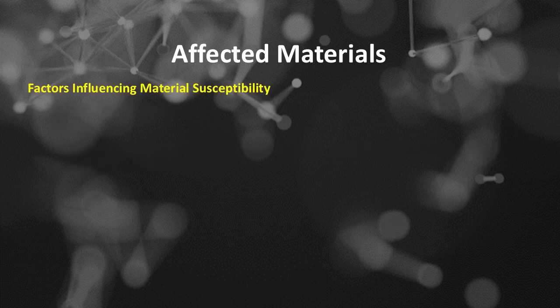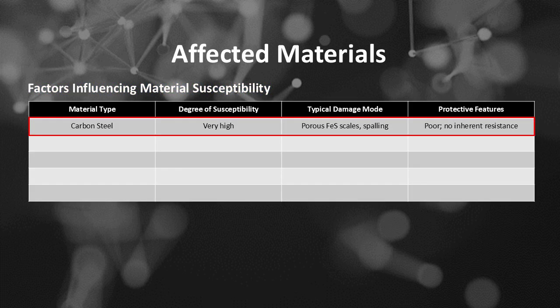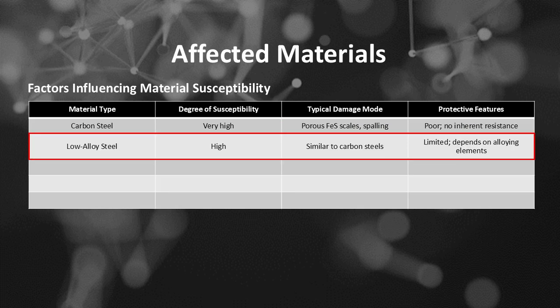Factors influencing material susceptibility. If material type is carbon steel, then degree of susceptibility is very high, its typical damage mode is porous FeS scales, spalling, and its protective features are poor, no inherent resistance. If material type is low alloy steel, then its degree of susceptibility is high, its typical damage mode is similar to carbon steels, and its protective features are limited, depending on alloying elements.